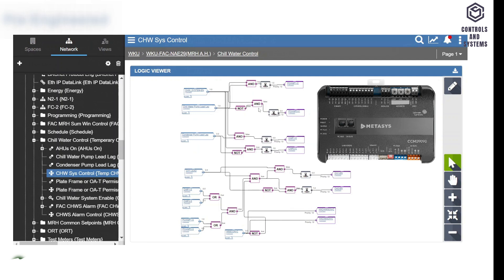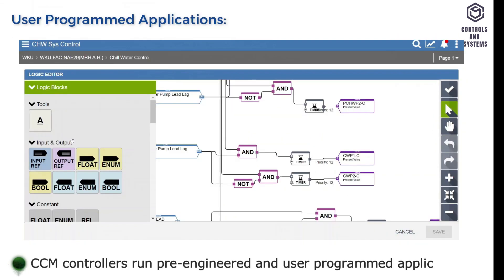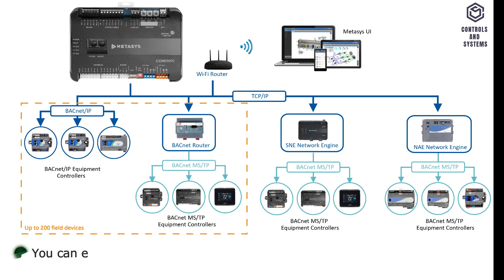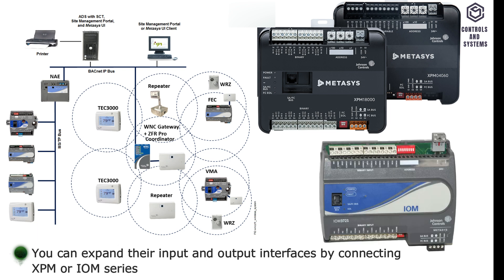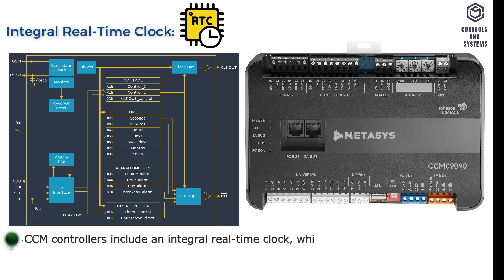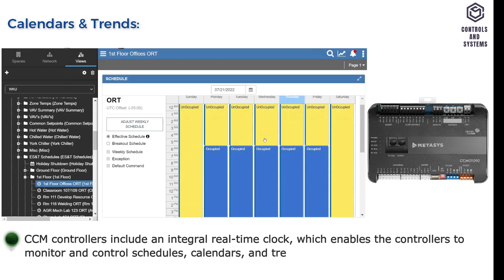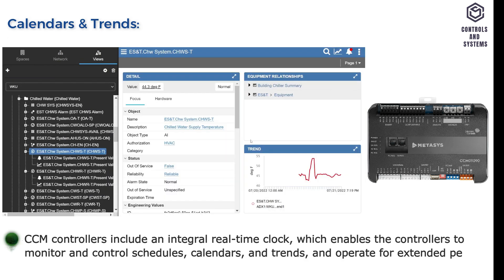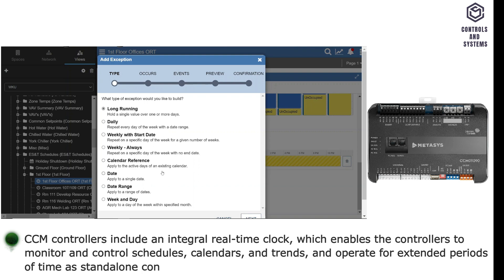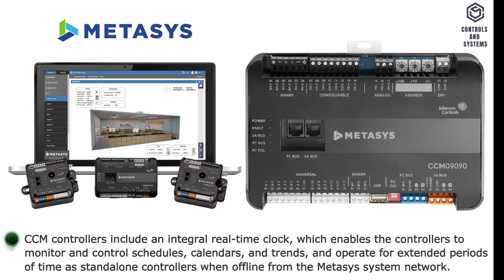Device Overview. CCM controllers run pre-engineered and user-programmed applications. You can expand their input and output interfaces by connecting XPM or IOM series I/O expansion modules. CCM controllers include an integral real-time clock, which enables the controllers to monitor and control schedules, calendars, and trends, and operate for extended periods of time as standalone controllers when offline from the MetaSys system network.